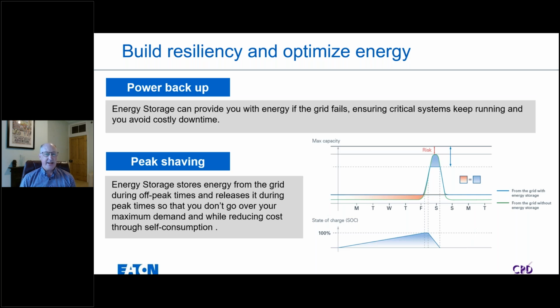So we might need a transformer upgrade, we might need cable reinforcements, we might need upstream reinforcements, and we can use a battery energy storage to help mitigate that by charging the battery when we have lower building demand and releasing that energy at those times when the building demand is peaking and putting a strain on our supply capacity.